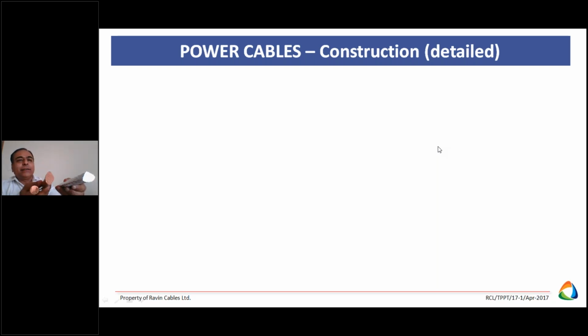Sir, why do you need round conductor shape, just a basic doubt? You are putting all these small wires into a group. Instead of that, suppose if you use a directly single conductor of some diameter instead of putting number of small wires - my doubt is why can't we use a single diameter directly, is this possible for me? That is possible to make a bend - that is the reason, very good question, why we are making wires instead of a single conductor with the same diameter, suppose this is 50 square mm or 70 square mm.